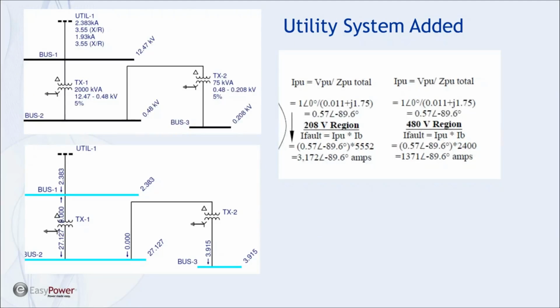So I added this. This is showing the EasyPower plug-in of this system here, the utility, in EasyPower. I plugged in the actual utility system and my 2000 kVA, my 75 kVA transformer, and you can see we get 3915 amps there doing it that way. And I think that's the end of my presentation.